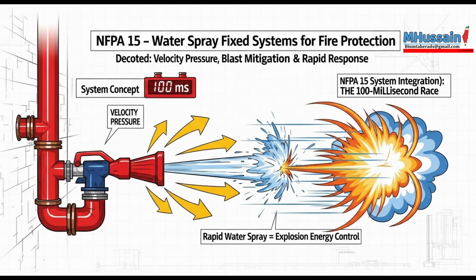But maybe the toughest part is predicting the cascading effects. Like what else might happen? Which systems might activate? How does that impact operations? Does the analysis show a need for explosion-proof electrical gear? How might blast pressure travel through the facility? That feeds back into the structural shielding we talked about earlier. It forces the design to consider not just fire, but a potential blast, which happens much, much faster.